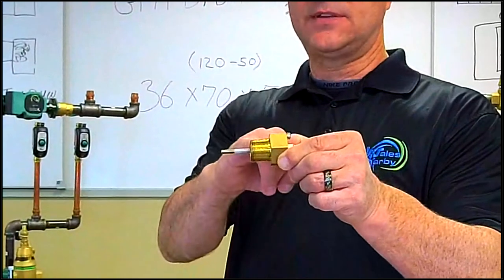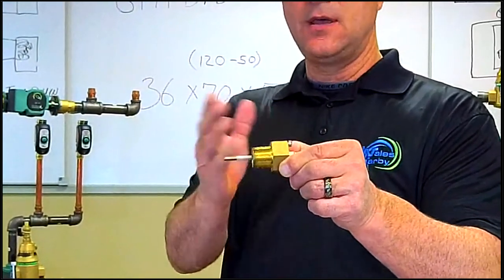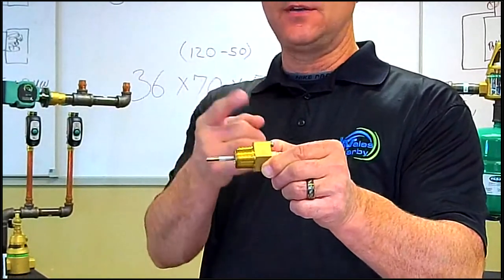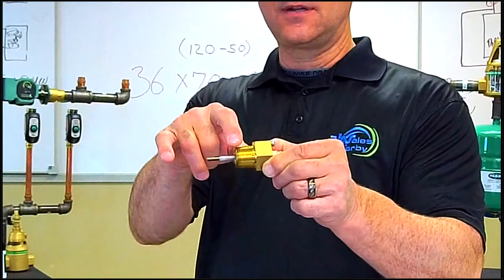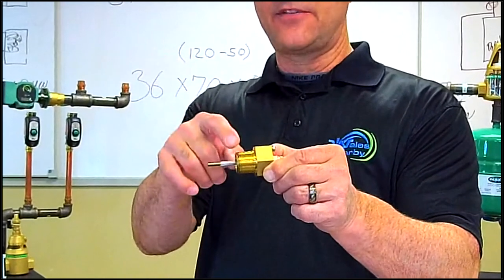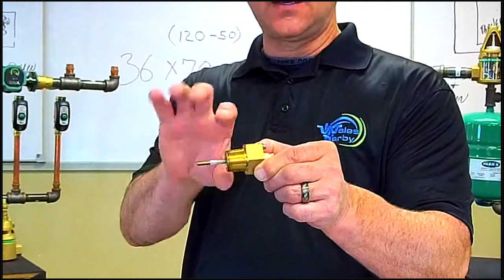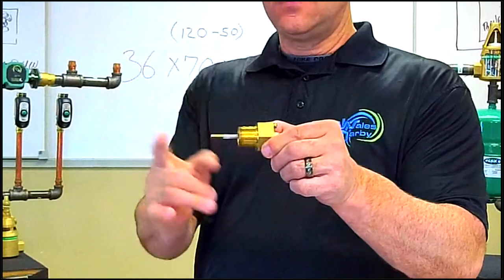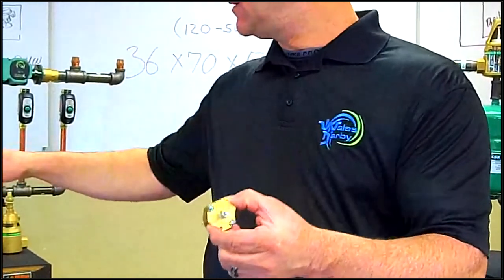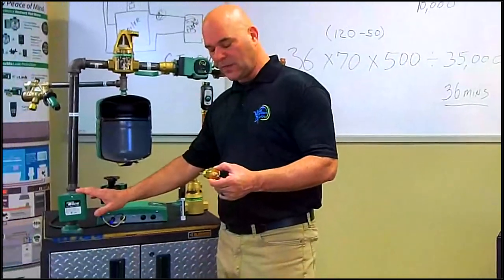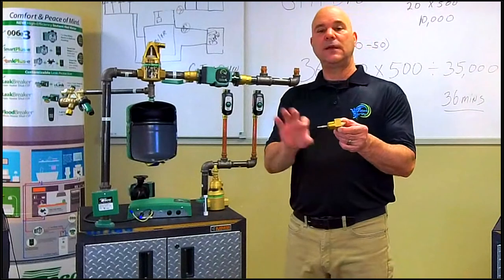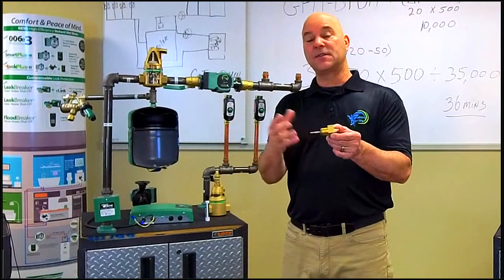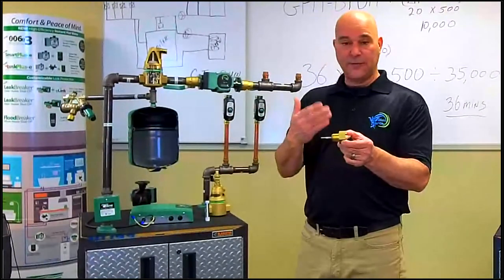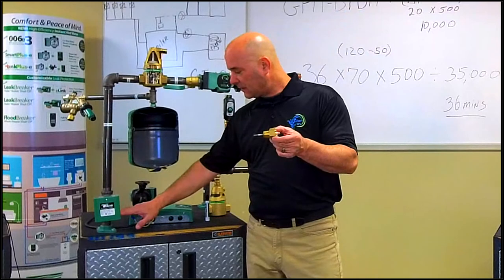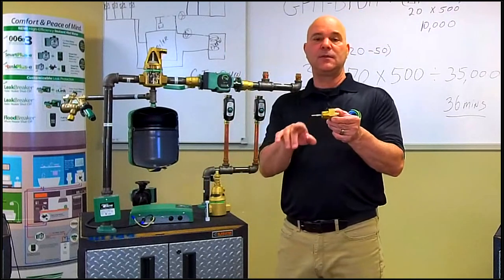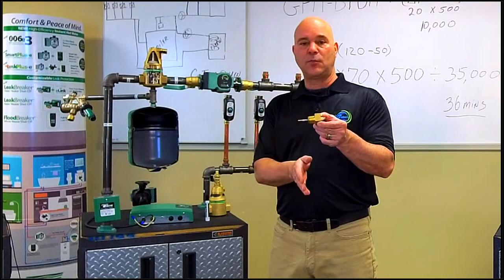And the goal here is, when we put this in, we had a couple questions in the last session we did. So when you put this in, read the manufacturer's instructions. They're going to tell you whether they want you to use dope or paste or tape. And they're going to tell you if they want one or two threads exposed. Depending on the manufacturer, they may have different guidelines. That's to make sure that we can have a ground. This rod connects right here through this nut directly to the low water cutoff. And what that does is this sends a signal, and this signal goes into the water. The minerals in the water allow this to see a ground connection. And if we lose water below this level in the boiler, we'll lose the continuity that we have on this ground, and we'll shut the boiler down.